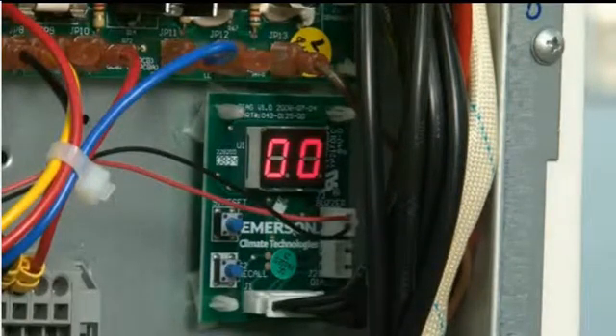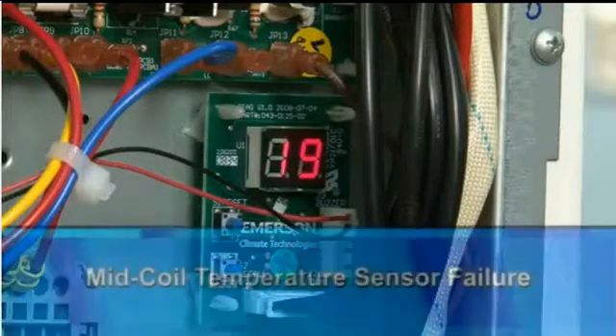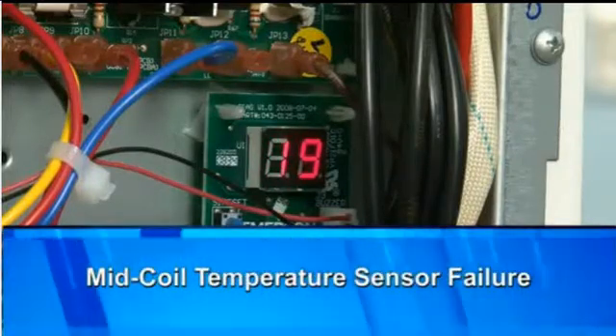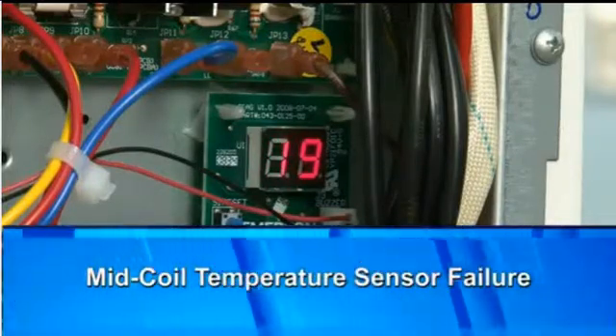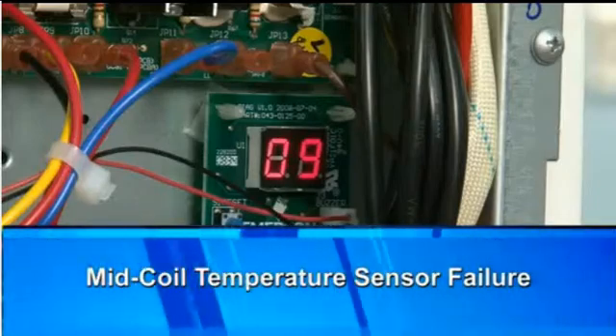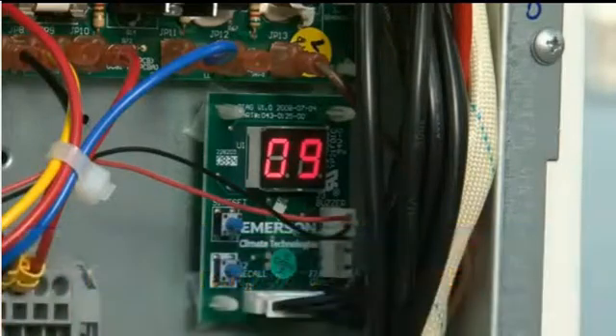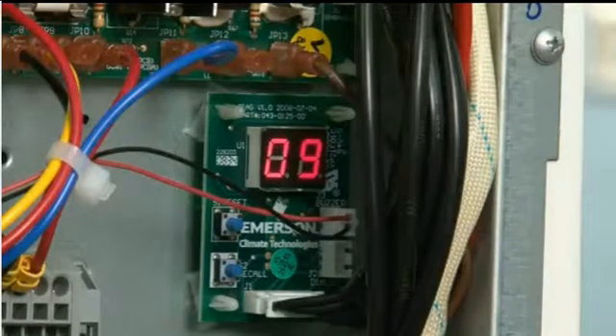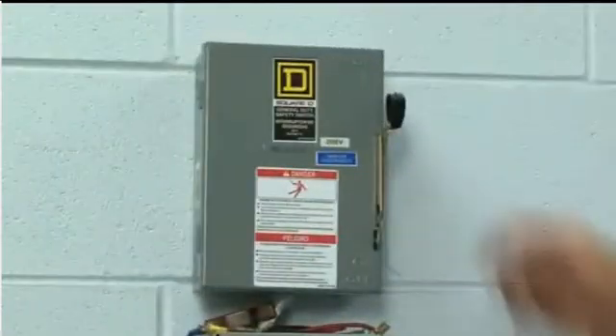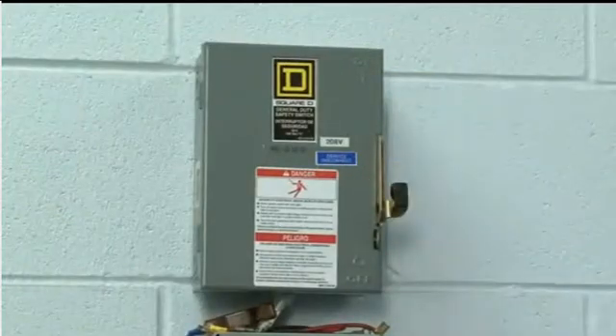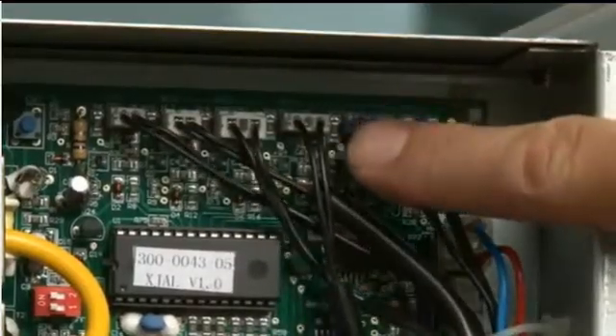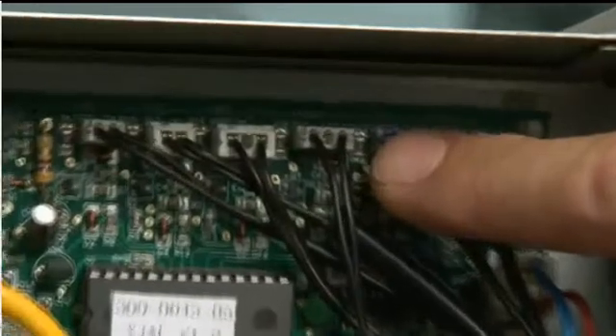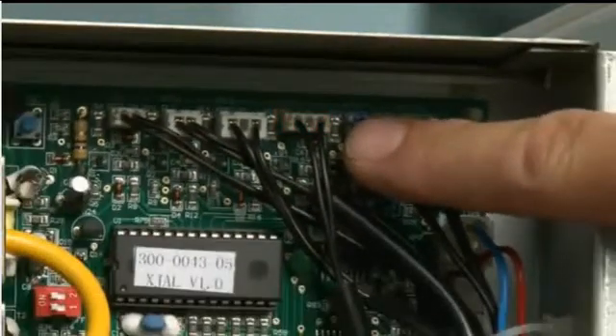Another example of an error code and the resulting fix is a mid-coil temperature sensor failure, error 19 when the compressor is on, and error 09 when the compressor is off. To troubleshoot this error, we need to remove the sensor and replace it with a new one. First, disconnect the power from the unit and determine that it is safe to work on the system. Next, find the sensor on the main control board, RT4, and remove it.